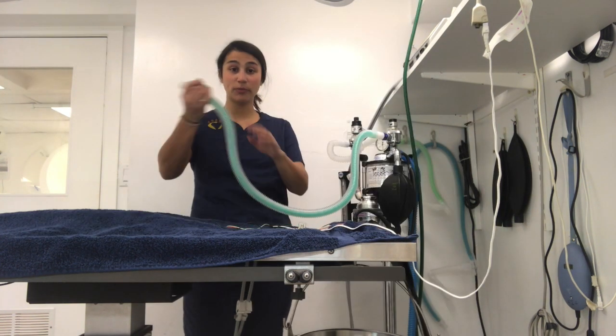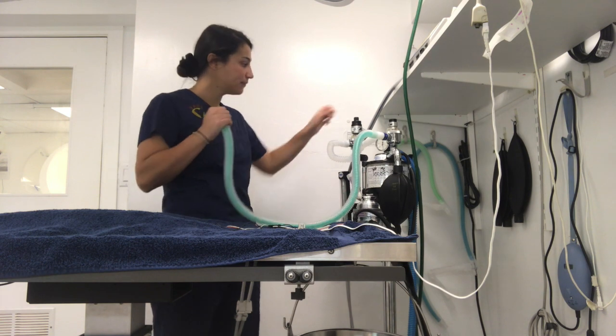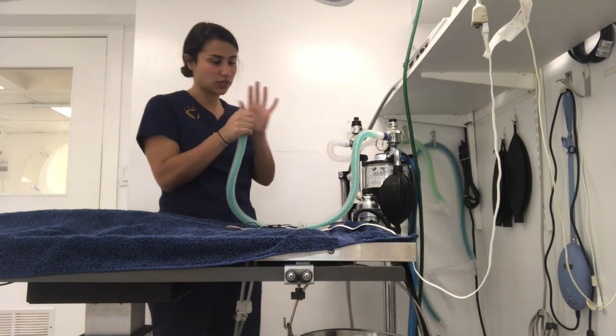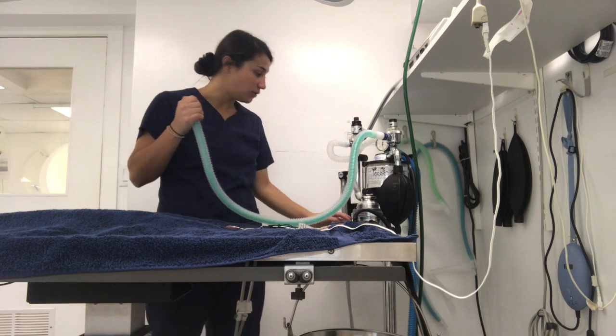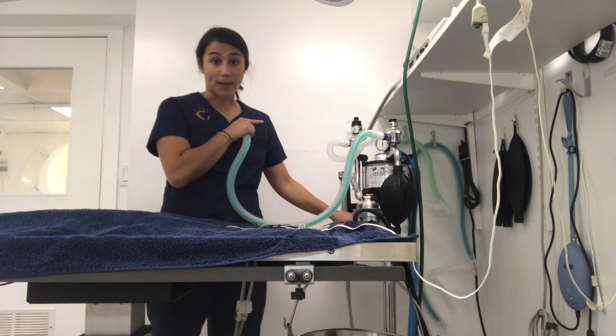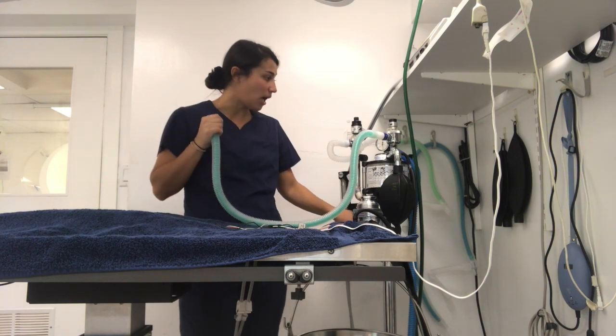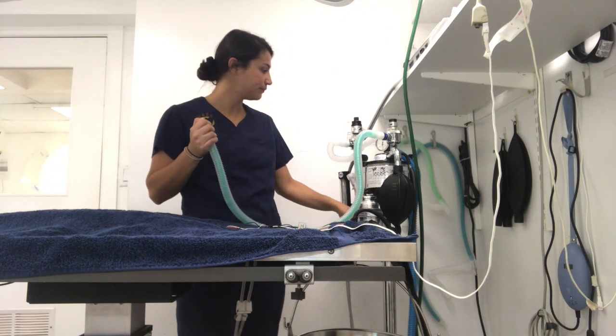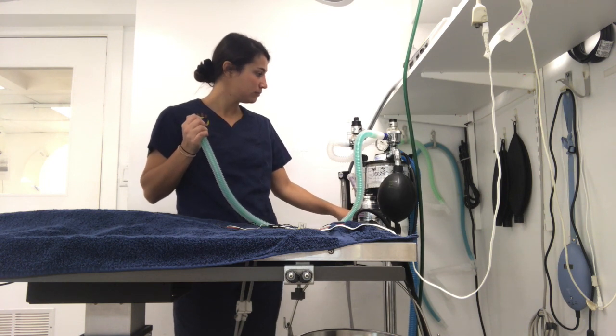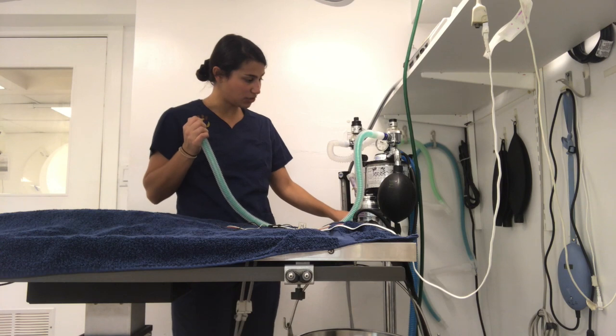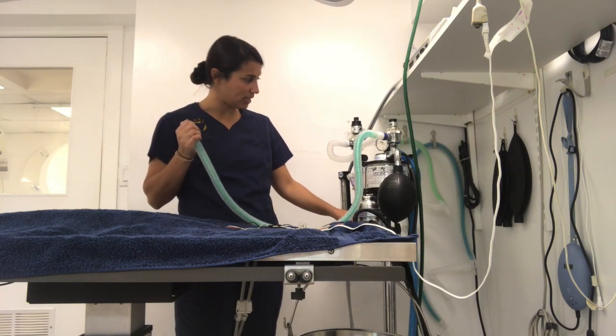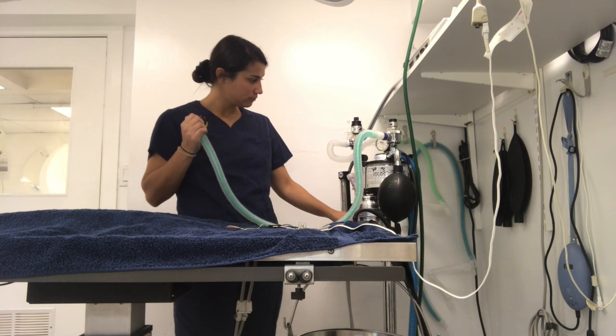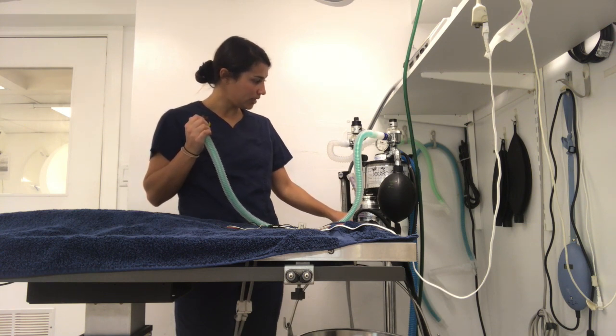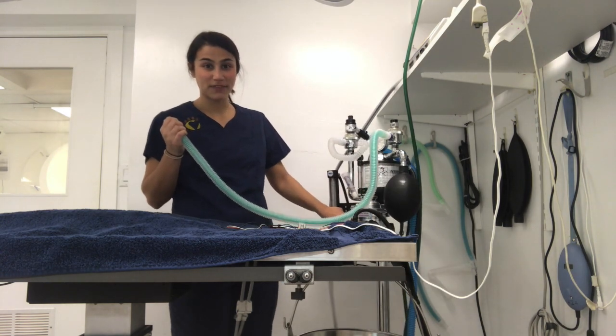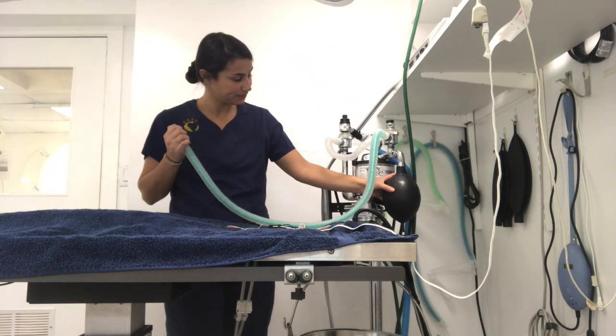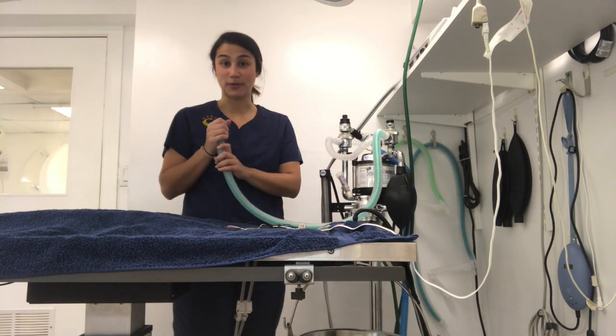So now I will be occluding our anesthetic tubing. The first step I took was closing off the pop-off valve. Now I will occlude the anesthetic tubing. Now using our oxygen flush and reading our manometer, I'm only going to flush it up to about 20 to 25. Then hold it for about 10 seconds and make sure that there are no leaks and that it is not going down at least 1 centimeter per minute. Doesn't look like there are any leaks, so that's perfect. See, my bag is still filled up. And that is how you perform a leak test.